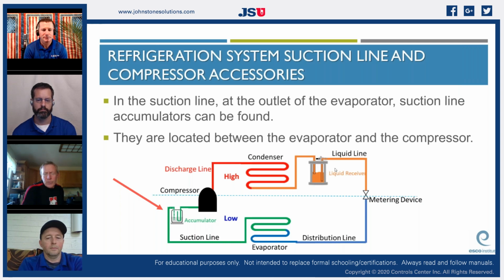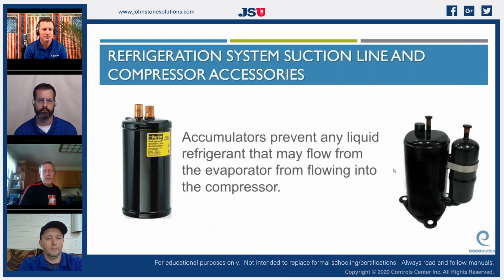Something I want to cover real quick, because I had guys ask me: the liquid line is where the receiver is. The receiver is usually in the high side and the accumulator is in the low side, usually prior to the compressor. Both are used for storing liquid refrigerant. We usually see accumulators in heat pumps because the conditions change when it's running. It's not utilizing the entire refrigerant charge, so we have to have a place to put that charge to not get it into our compressor.